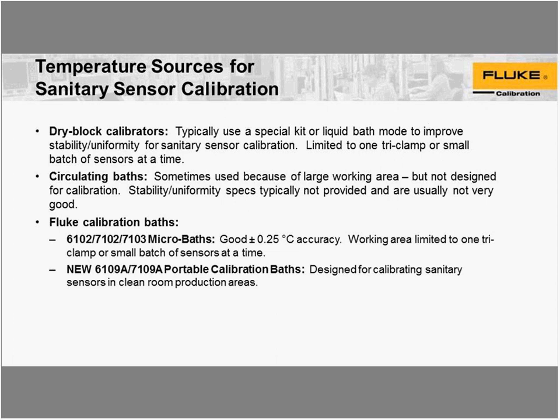A calibration bath is the dry block calibrator. This is a calibrated temperature where the display is calibrated. I should have mentioned that with the dry block calibrators. That's one of the features of a dry block calibrator as well, is that the display is calibrated. You can use that for temperature reference, temperature stability.